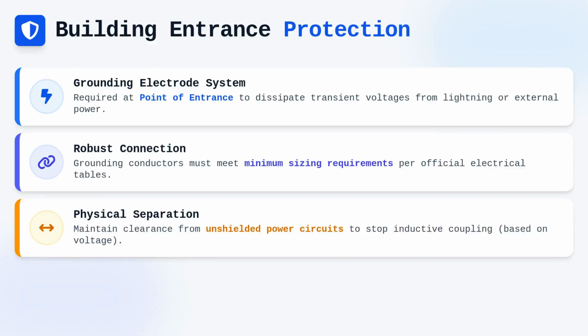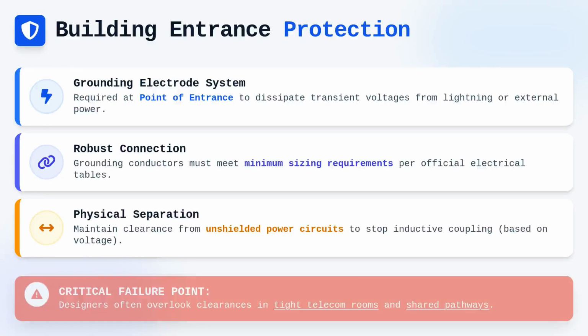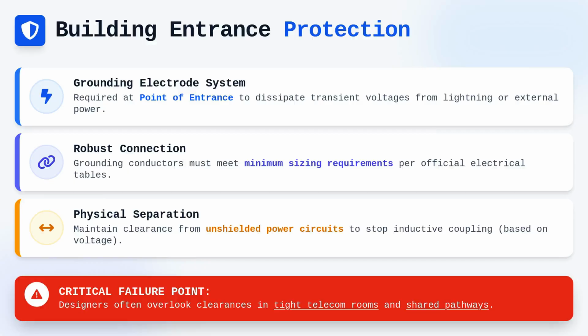Furthermore, we must maintain specific clearance distances between telecommunications cables and unshielded electric light or power circuits to prevent inductive coupling. These physical separation requirements are calculated based on the voltage potential of the power lines. When working within tight telecommunications rooms or shared pathways, failing to respect these clearances is a common point of failure for designers and contractors alike.